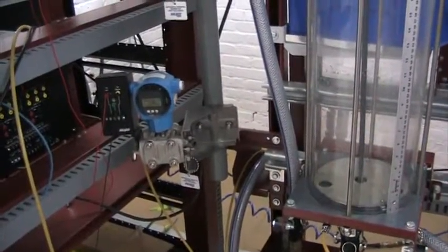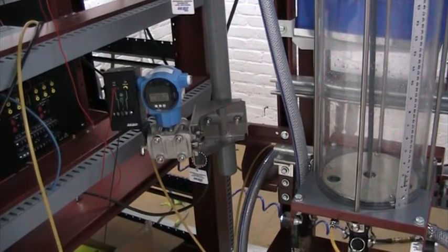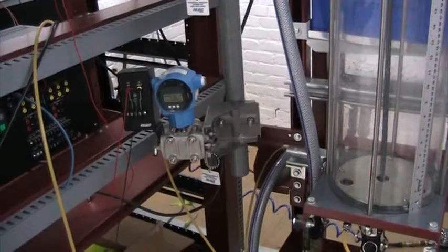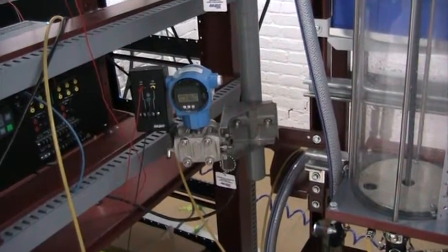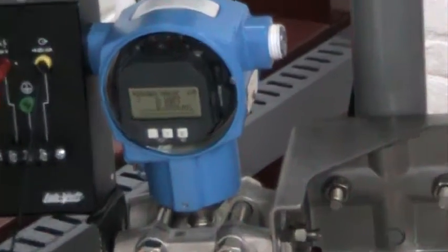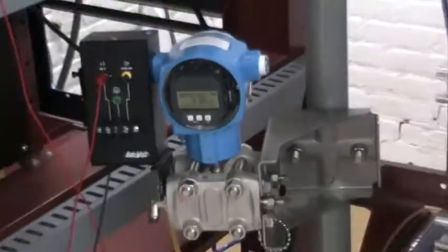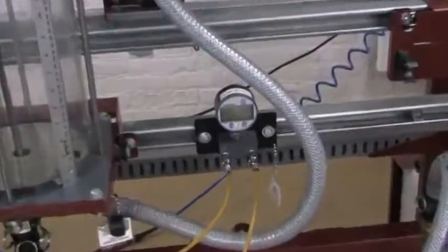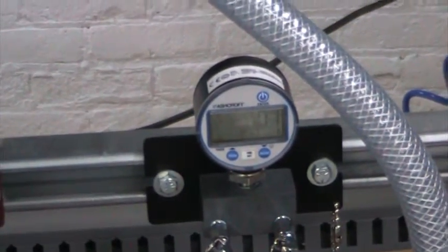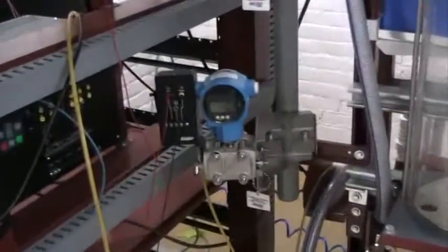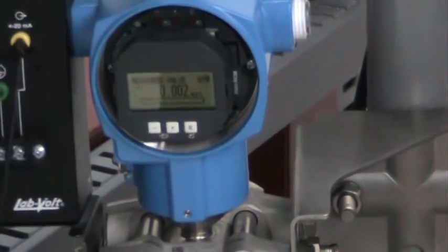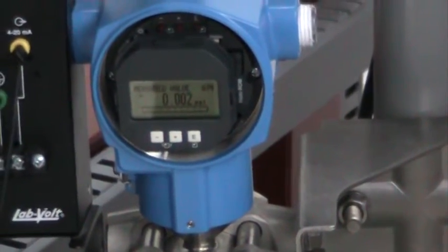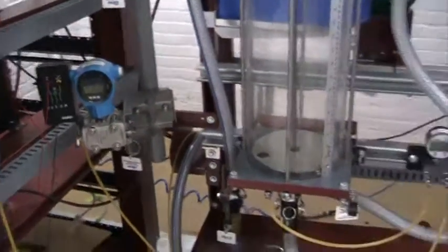And this is why I keep saying in my videos not to touch the instrument once you have completed your settings on it. And this right here is indicating 0.002, and that is in PSI. Okay. I could have spent more time to make sure that both of them are 0, but that would have required more time. And that's what you would have to do if you absolutely need a 0 for both of them when there is no water in my column.